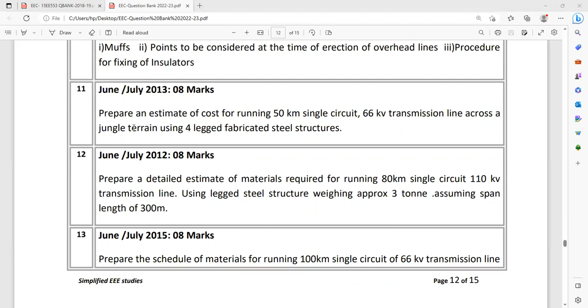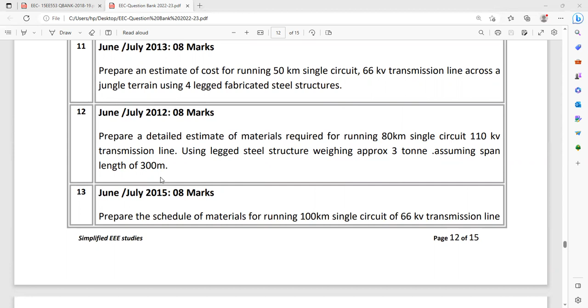Based on this parameter, the length of the wire can be computed, and you have to remember the rest of the materials. Similarly, prepare the detailed estimate of materials required for an 80 kilometer single circuit 110 kV transmission line using a legged steel structure weighing approximately 3 tons, assuming the span between two poles is 300 meters. That's a similar kind of question - you mainly have to remember the materials.